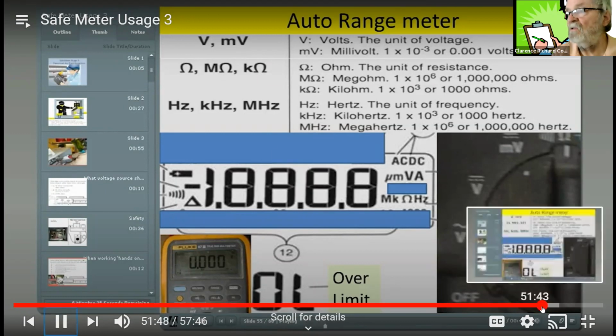FYI, there is 1,000 ohms to a k ohm, 1,000,000 ohms to a meg ohm, 1,000 millivolts to a volt, and 1,000,000 microamps to an amp. The manual ranging meter forces the operator to adjust the selector to the proper range, making the operator aware of the units of the value being displayed. The operator must make a conscious effort to interpret the engineering units when reading the value.